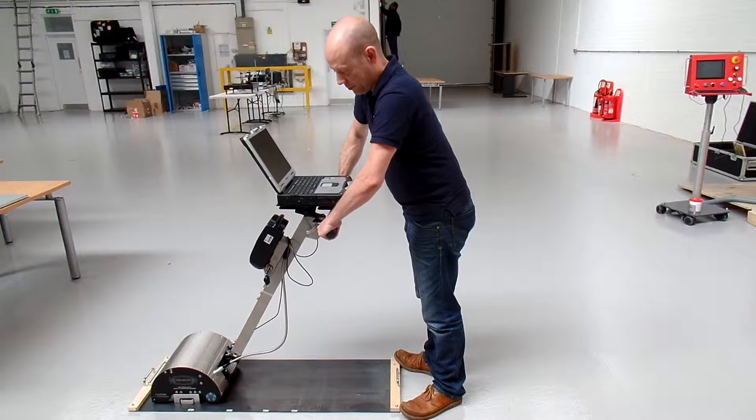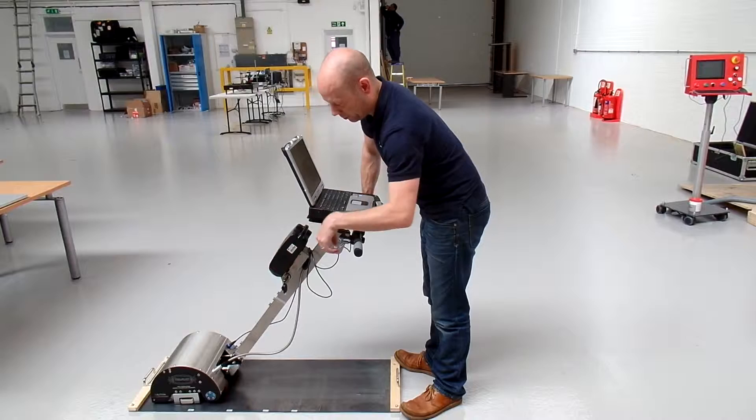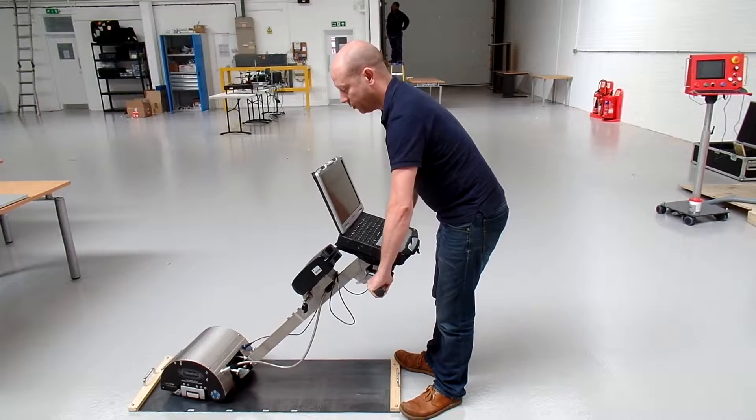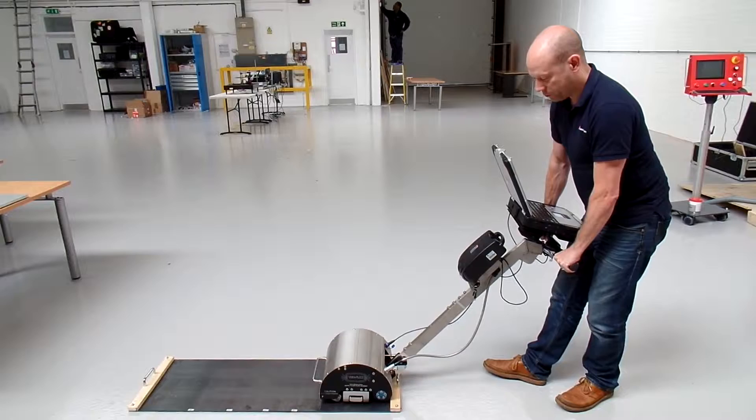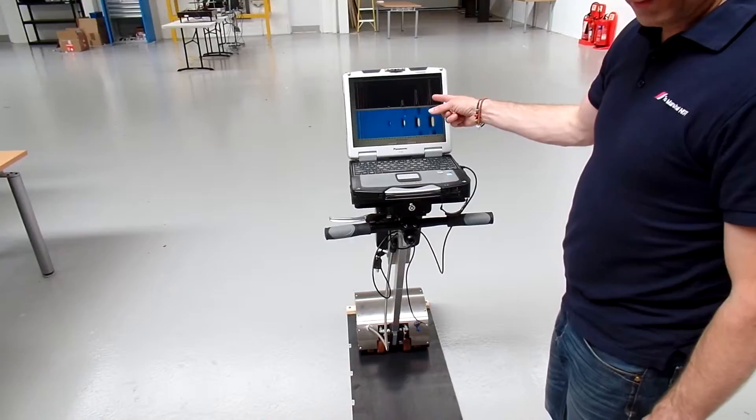There is a lever here on the handlebars which, when you pull, engages the motor to allow you to drive the TruFlex over the calibration plate. You can position the scanner and press down on the handlebars like so. That operates an innovative mechanism in the scan head which allows the magnets to be lifted from the plate with very little effort. The scanner can then be repositioned to form the start of the next scan or wheeled back as appropriate and then re-engaged with the plate. Press the calibrate button, then using the lever on the handlebar, drive forward. Then press the calibrate button a second time to see the result of the calibration.